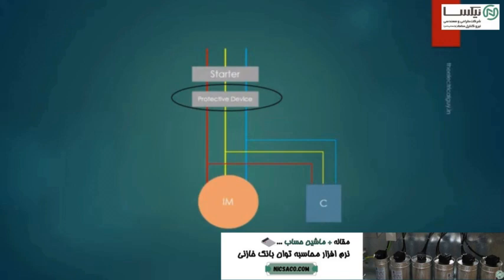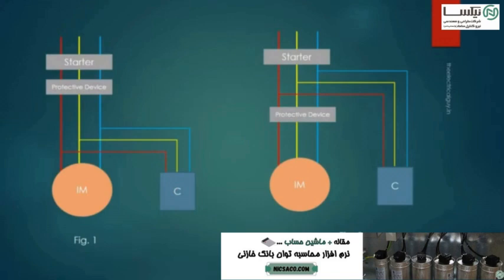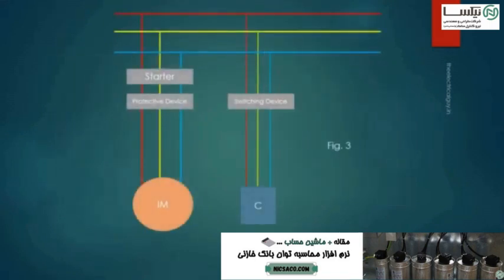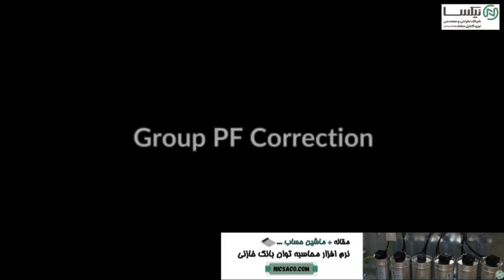In case of direct connection, as shown in figures 1 and 2, there is a risk that the motor keeps running even after the disconnection from the supply because of the residual kinetic energy, and it will self-excite with the reactive energy drawn from the capacitor bank and may turn into an asynchronous generator. Hence, to avoid this, it is strongly recommended to use a separate switching device for the capacitor bank as shown in figure 3. When using the connection shown in figure 3, the capacitor bank is switched on after the motor is switched on, and it is turned off before the motor is turned off, which avoids the running of the motor after it is turned off.